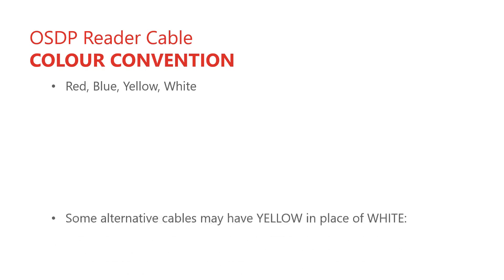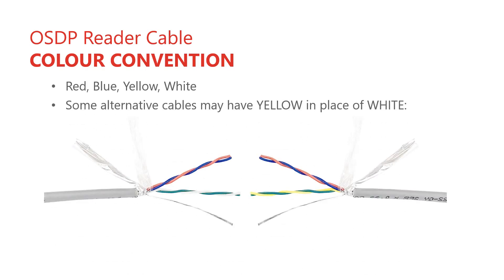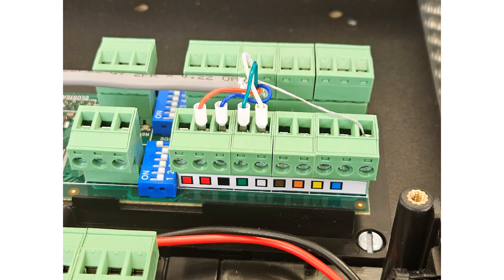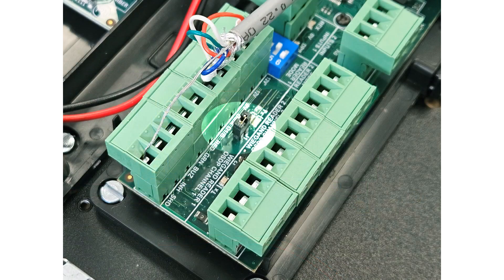Prepare the OSDP reader cable the same way as the RS485 cable, with bootlace ferrules on the cluster module end of the cable only — no ferrules on the reader end. Here is the advised wiring convention for the reader port: wire the red to 12 volts, blue to 0 volts, green to D0/A, and white to D1/B. Wiring the screen drain to SHD can help if there are concerns about electromagnetic interference. Connect the terminating jumper to the reader cable you are using — J1 for reader 1 and J2 for reader 2.